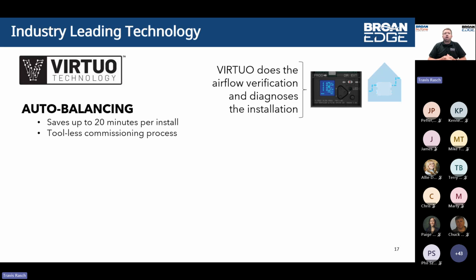This Virtuo technology is going to automatically balance the airflows. You will not be required to use any kind of tools to commission the product or make any external adjustments. All of the commissioning is going to be done at that LCD screen with those related buttons. So the first time this unit gets powered on, it's going to provide you with the maximum CFM the unit can achieve, given the ductwork route and the application. It's going to provide you that max CFM.